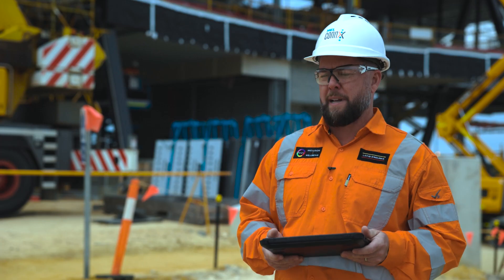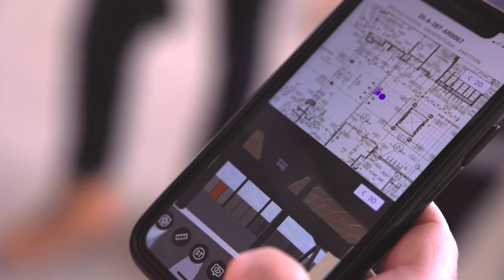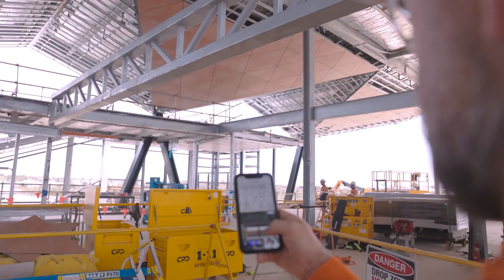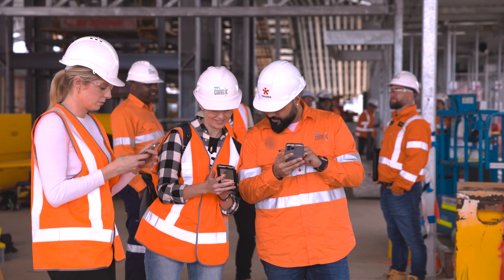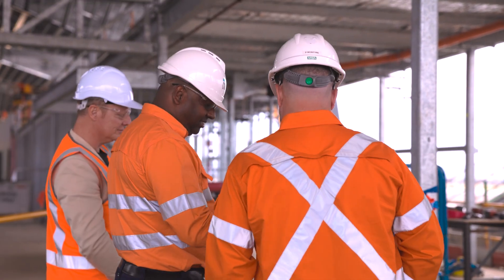Having all the information — 2D drawings, 3D model, all the issues — located together in one platform and easily accessible has been a huge benefit and saves a huge amount of time. A lot of the team use the phone app; they find it easy to use, convenient, and it's always in your pocket. We once forgot our tablets and decided to use the model on our mobile apps — we were pleasantly surprised. Using the model on mobile, we identified issues in an electrical room where a distribution board that was installed was different to what was designed, and we immediately raised an issue to the site team for redline markup.